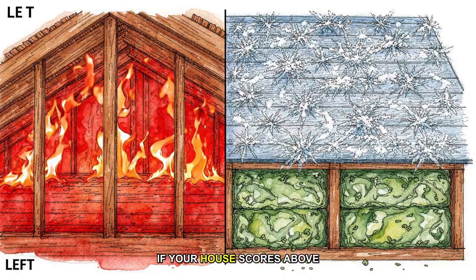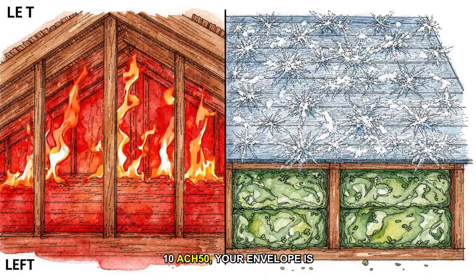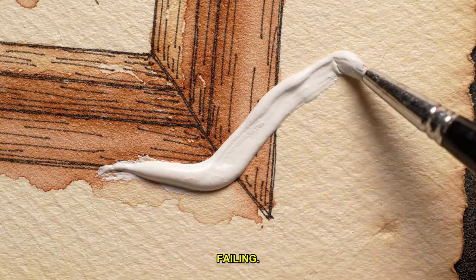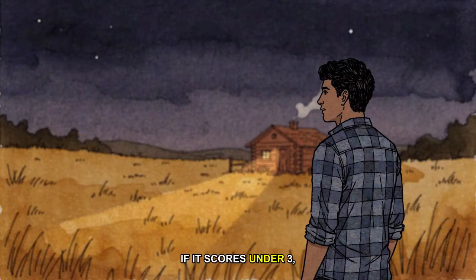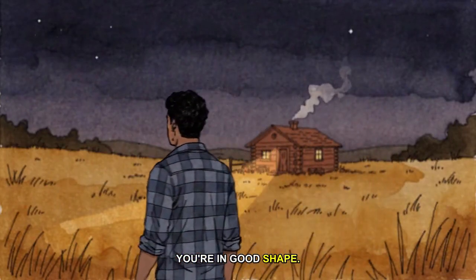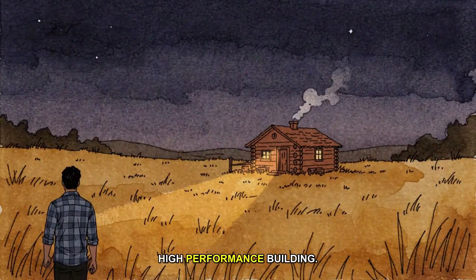If your house scores above 10 ACH 50, your envelope is failing. If it scores under 3, you're in good shape. Under 1, you have a high-performance building.